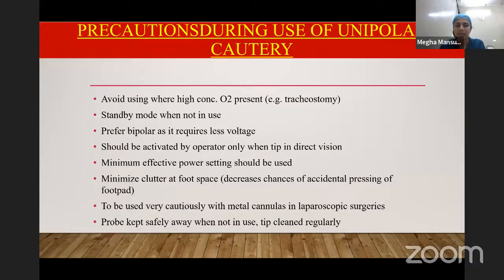We should keep the setting such that minimum effective power is used. Foot space clutter should be minimized because it reduces chances of accident. We should use it very cautiously where metal cannulas are used in laparoscopic surgeries. As we have discussed, it can lead to capacitance coupling and passage of current to the patient. The probe should be kept safely away when it is not in use, and the tip should be cleaned regularly.